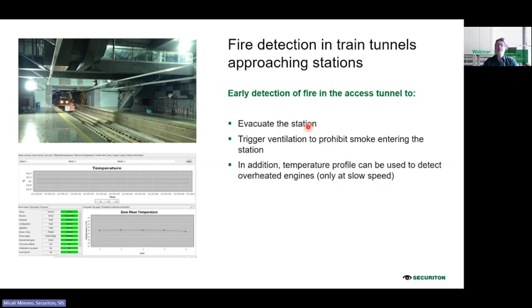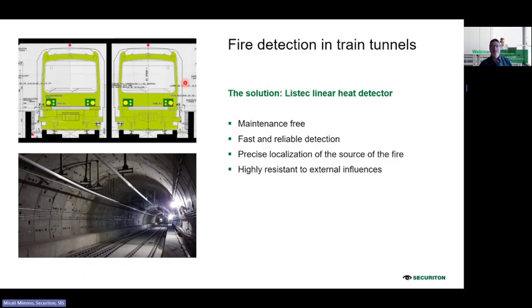And then in addition, if you have a system which is integrated in the SCADA system, you see the profile of the temperature. And if there is a train which is stopping here on the platform, we are also capable of detecting an overheated engine. If the train is passing very slowly or stops for a few seconds, normally the sensor cable will be installed on the lower part when we reach the platform, then it goes up again, and then it continues on the roof. So during this period, because we can detect infrared radiation, it's possible to receive some information about an overheated engine. This is also interesting for the operator.